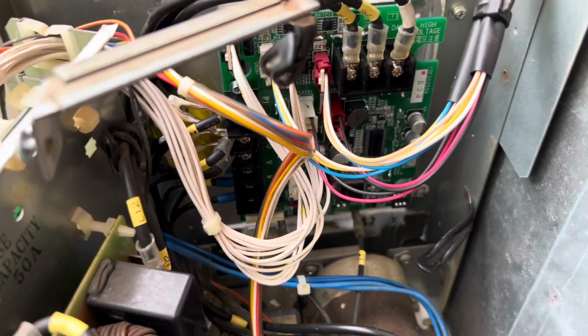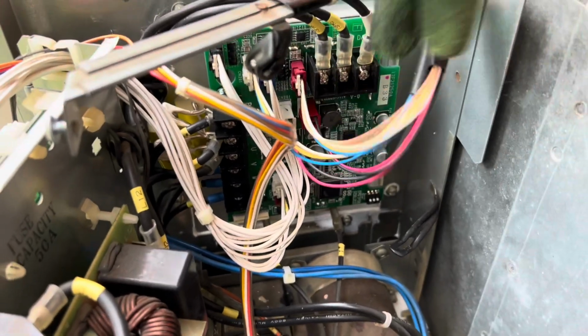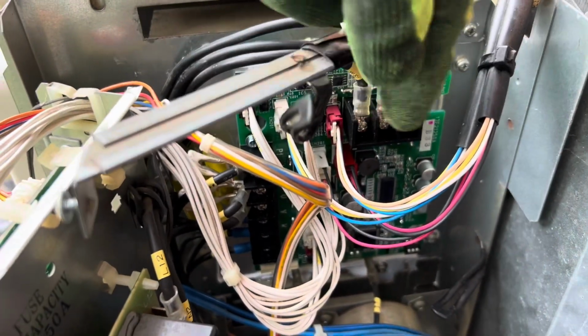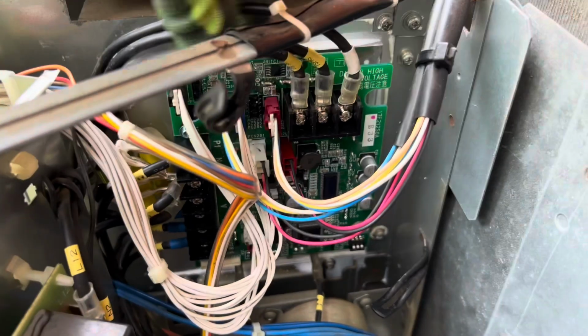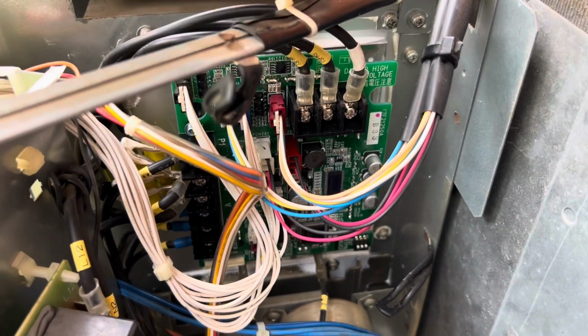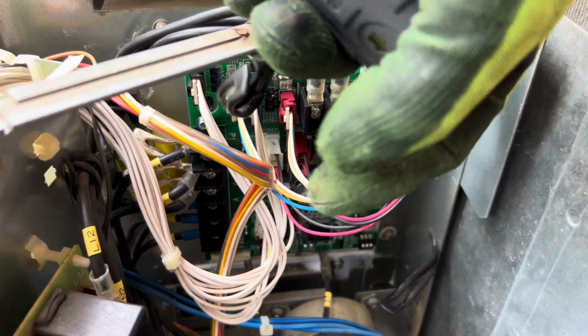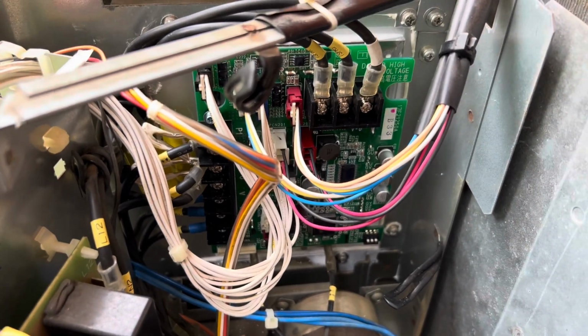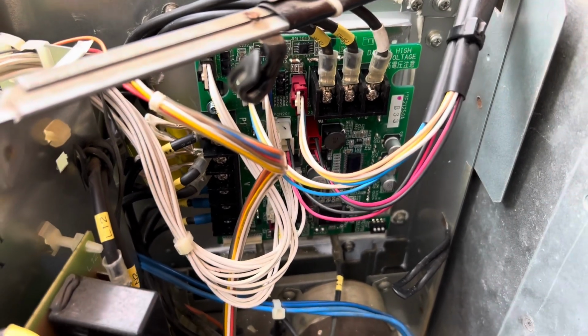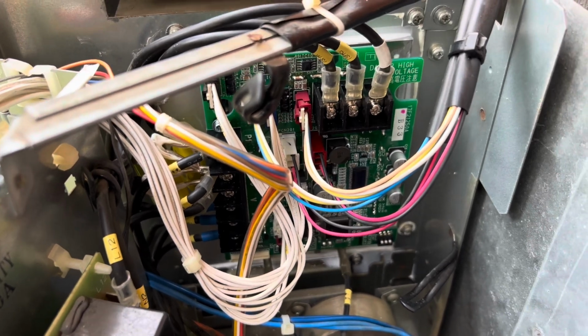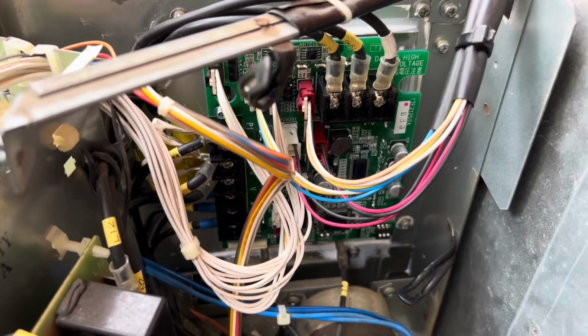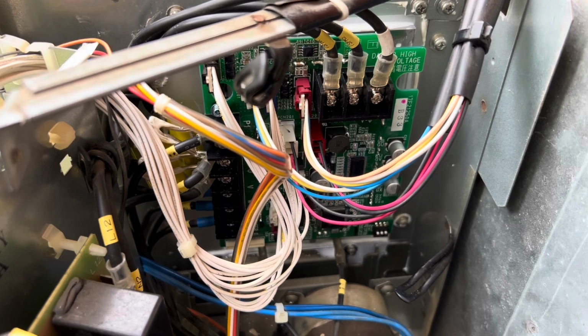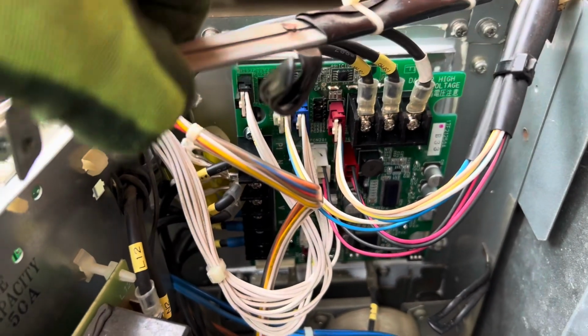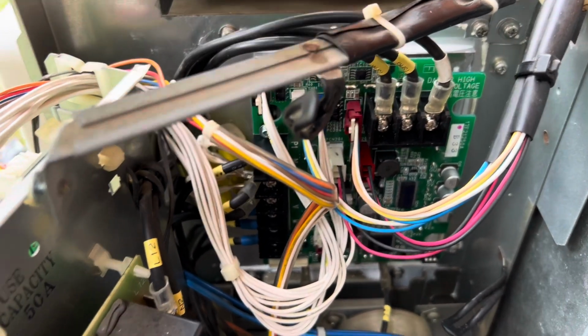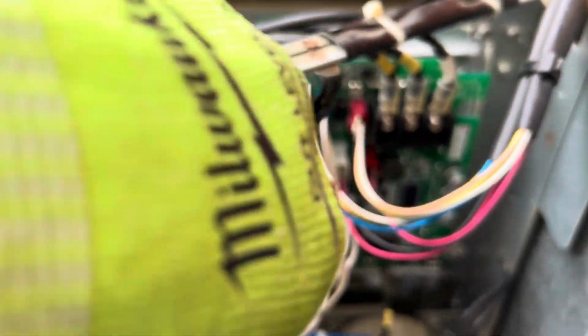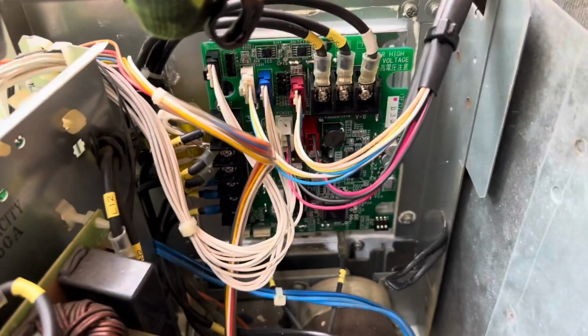The inverter board here not only drives the compressor, but it drives the fan motors too. I had a look through the manual and couldn't find any way of testing those - they have these two leads here. So all I did from memory last time was compare them to each other, spun them to check, and compared whatever readings I was getting to the other ones - they were all the same. Some didn't quite match, but they lined up enough that I'm happy to say they seem fine. So we're pretty much ready to turn power on and see if this thing runs.